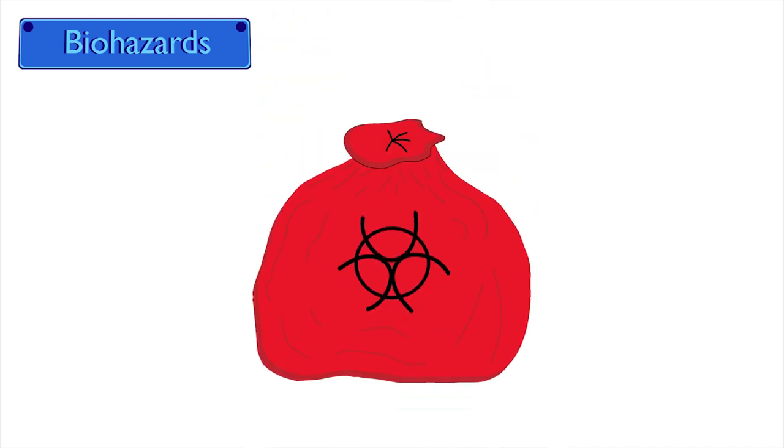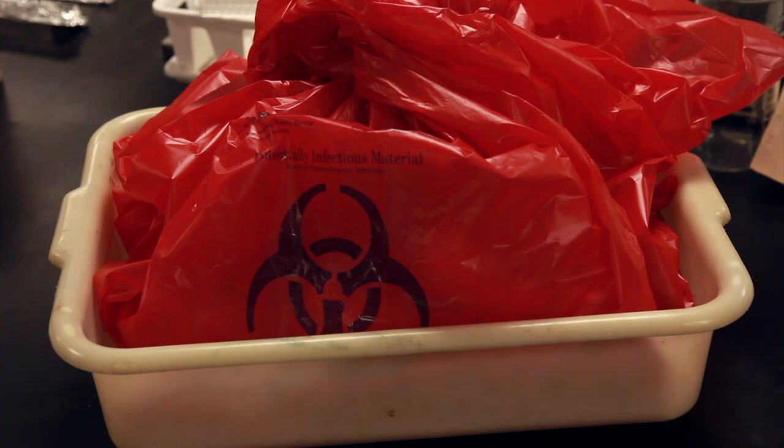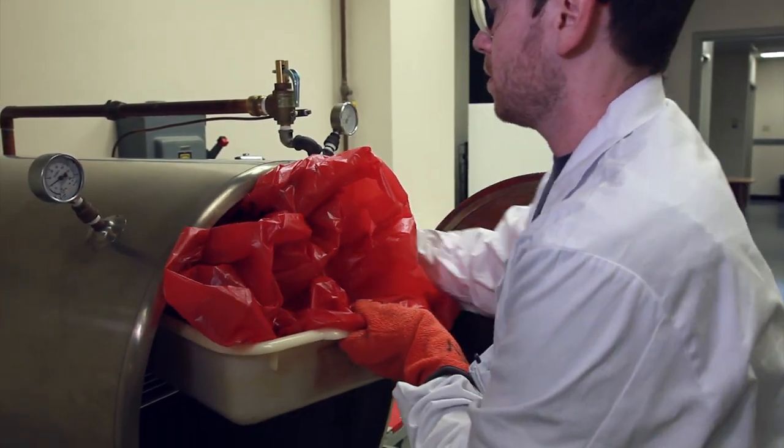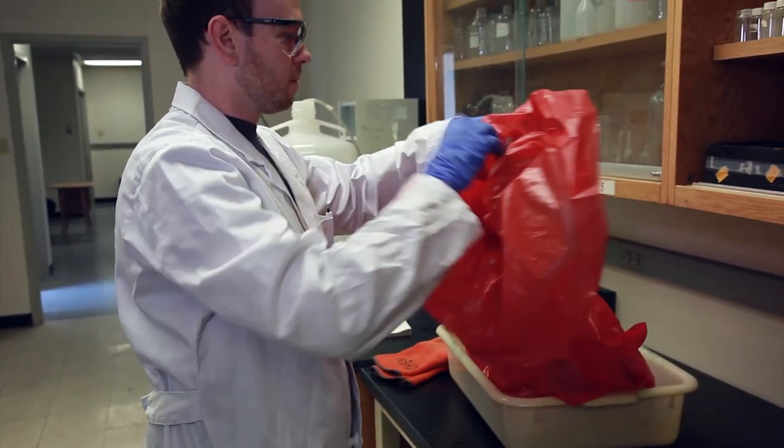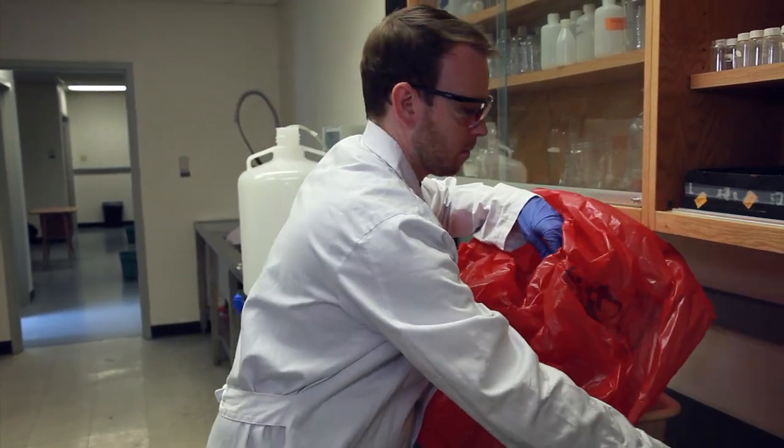Solid Biohazards and Biohazard Bags. When preparing solid biohazardous waste items, make sure that the waste is inside of a red or clear polypropylene autoclave bag that is clearly labeled with biohazard symbol on the outside and is the right size. If you have a small chamber, a large capacity autoclave bag will not fit and the items will not be properly decontaminated. When loading the biohazardous waste, do not overstuff or cram items into the bag. Pack items loosely to allow for steam to flow among items. Also, make sure to not fill the bag completely. You can fill it about two-thirds of the way instead. Bags packed to capacity with biohazardous waste will not properly sterilize, even if all the autoclave operating parameters are followed.